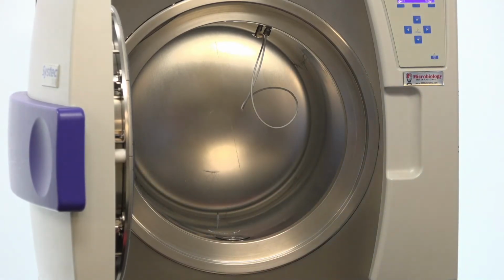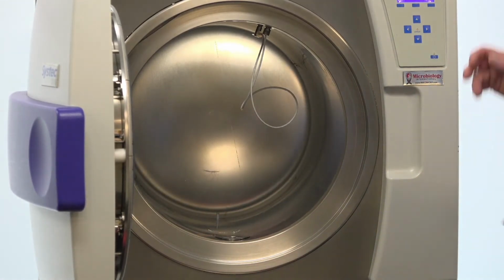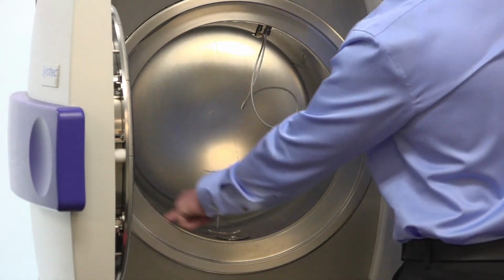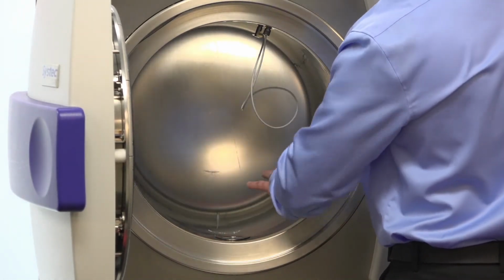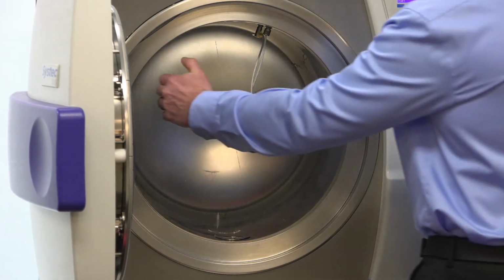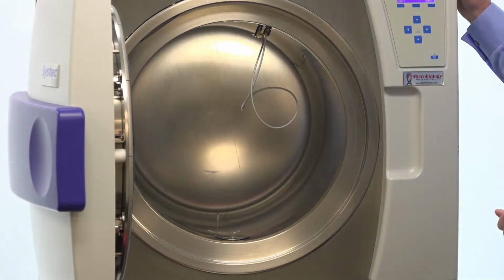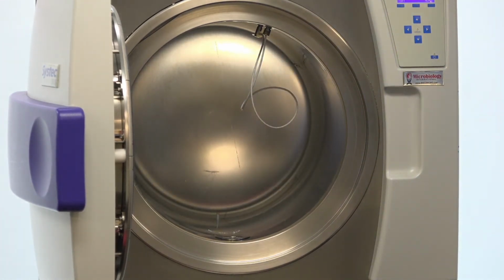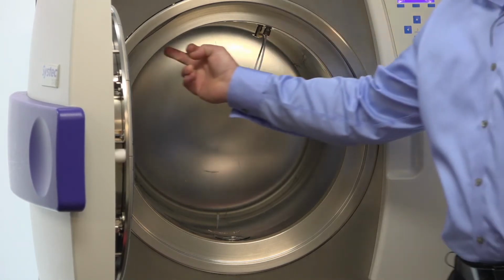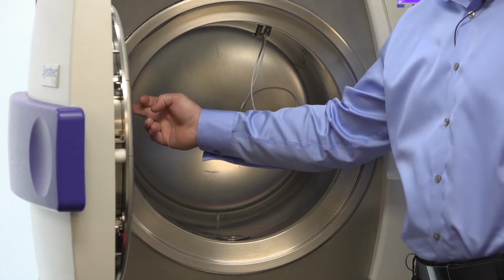So the cooling coils that we offer are going to be on the outside of this vessel, so your vessel is going to be really nice and clean with those cooling coils wrapped directly around. Now those cooling coils are not completely circular, because we gain a lot more efficiency by having them flat to the vessel. So they're rounded on the outside but flat to the vessel, so they have more surface area to contact the vessel.